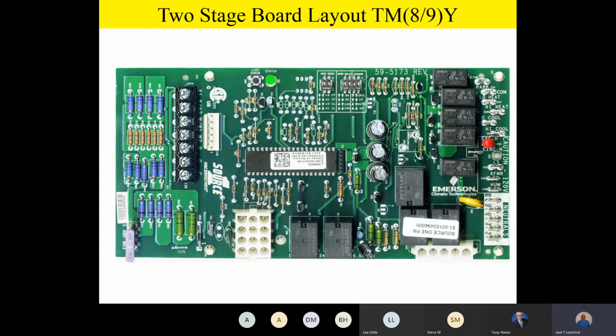So as we start on the left-hand side, team, like we did before, Y1 is your first stage cooling call. If you have a 2-stage product outside, Y2 is going to be your second stage cooling call. Because it's two-stage, W/W1 is going to be your first stage heating call.